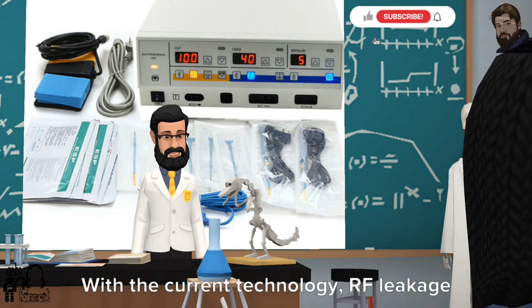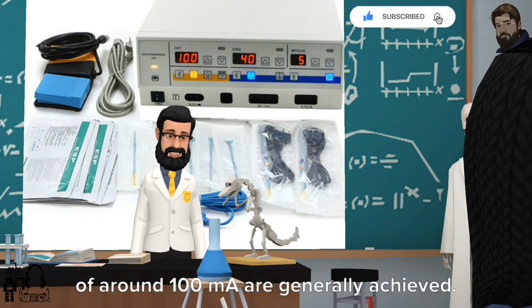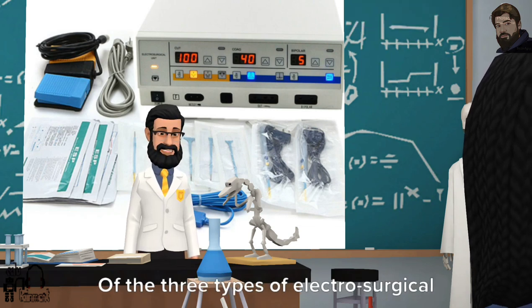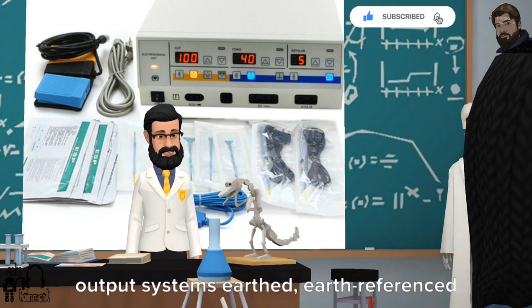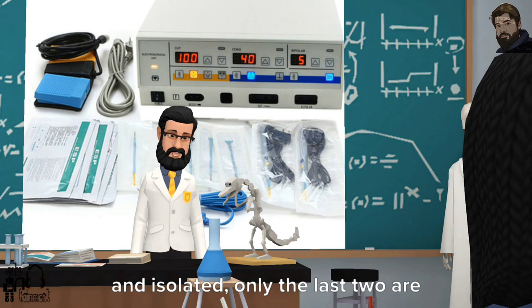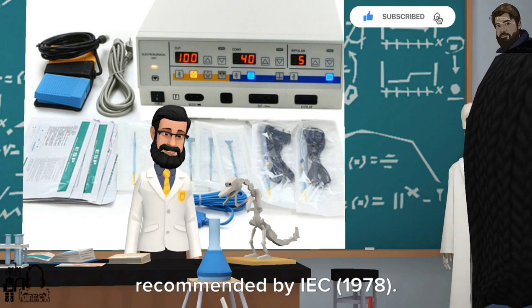With the current technology, RF leakage of around 100 mA are generally achieved. Of the three types of electrosurgical output systems (earthed, earth referenced, and isolated), only the last two are recommended by IEC 1978.